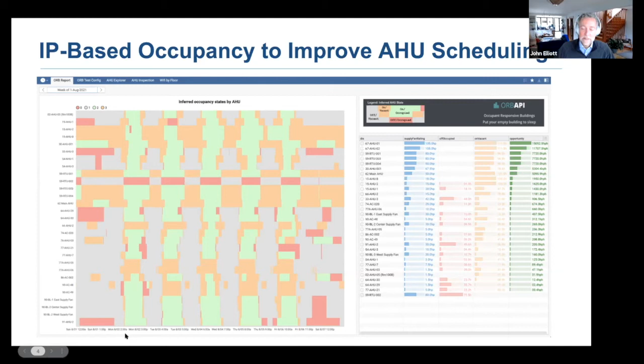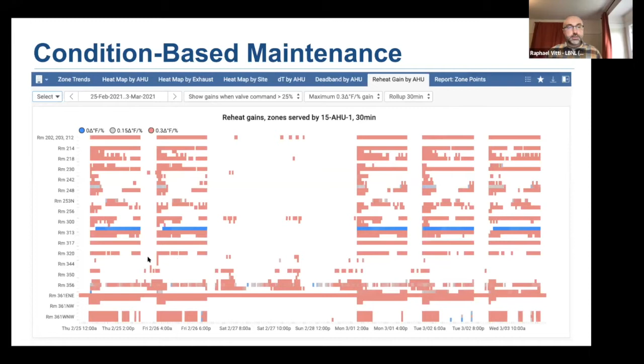Now, the next one is a calculation and a visualization that we created based on a specific request from our technicians on the ongoing commissioning team. We're using temperature data and reheat valve commands to calculate a metric that essentially shows whether we are getting the heating that we're expecting in our terminal units. A zone where the reheat coil is clogged or the reheat valve actuator is broken and the valve is in the closed position will show here in blue and be easily identified even when you're looking at 30 or 40 zones like we're doing here.